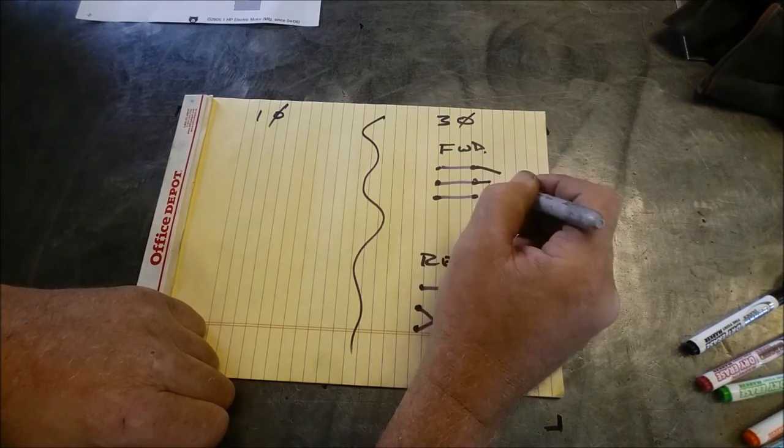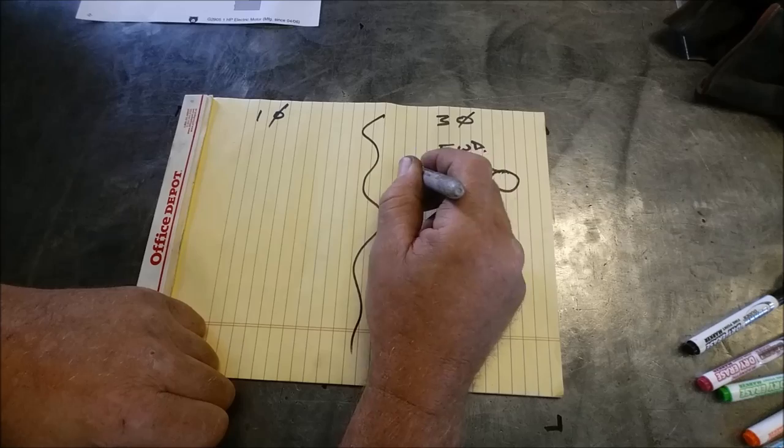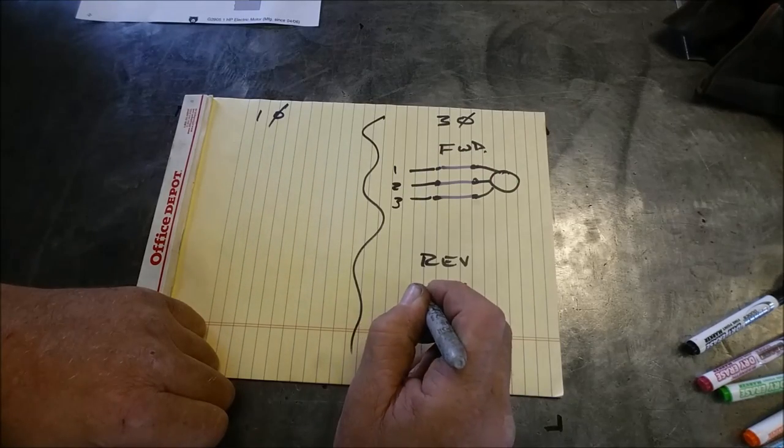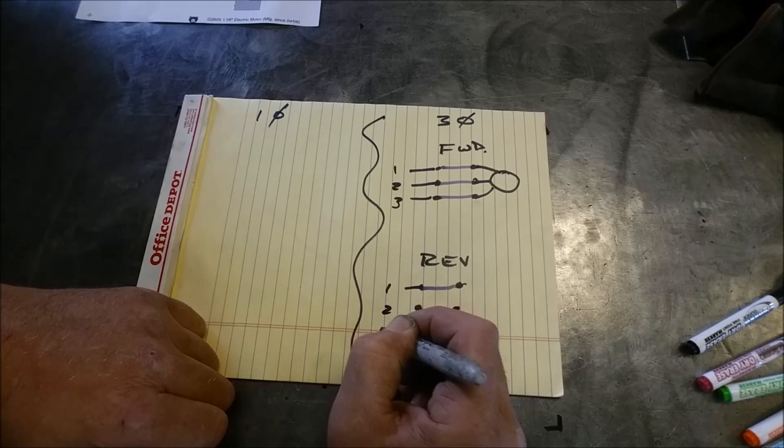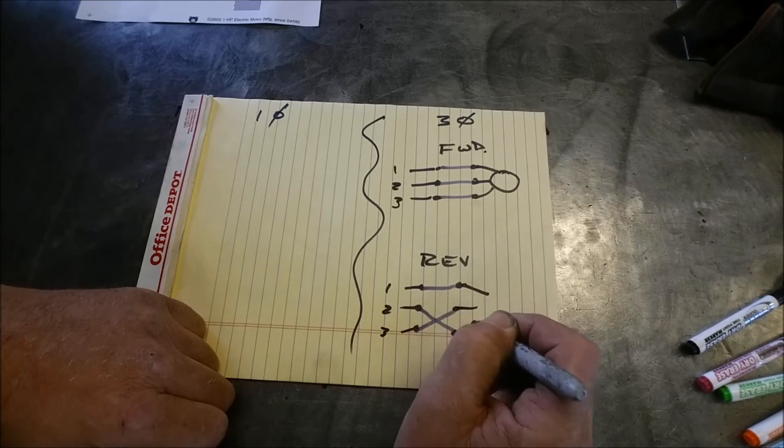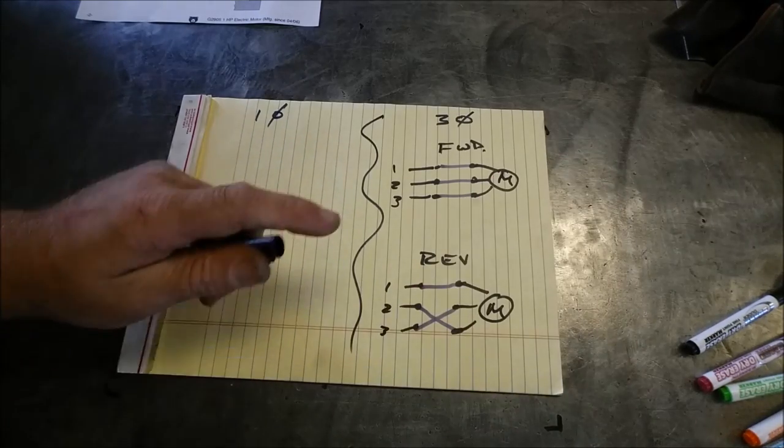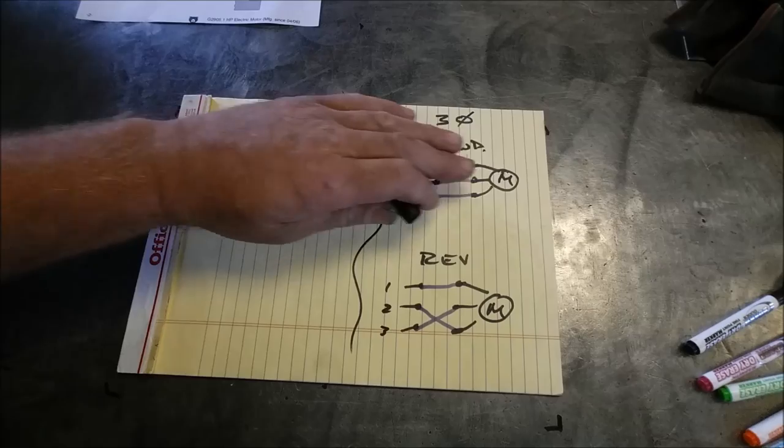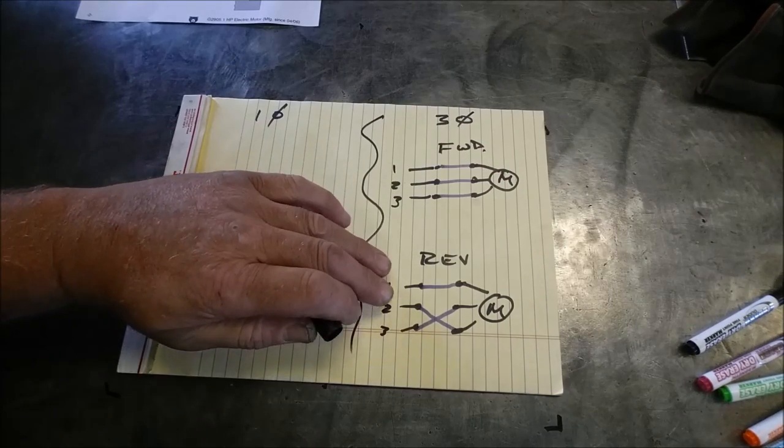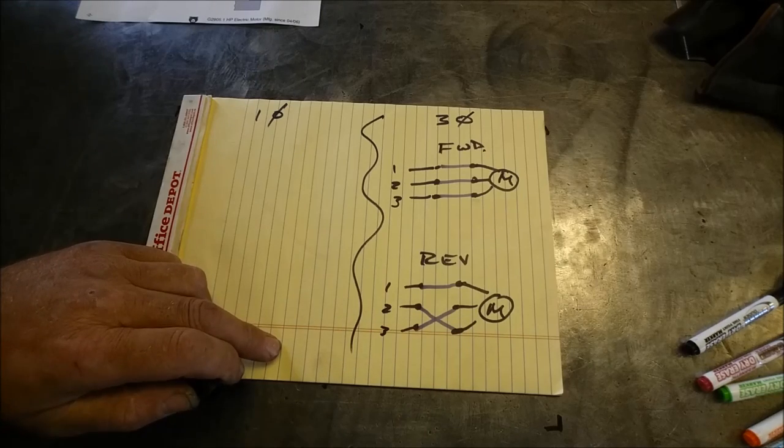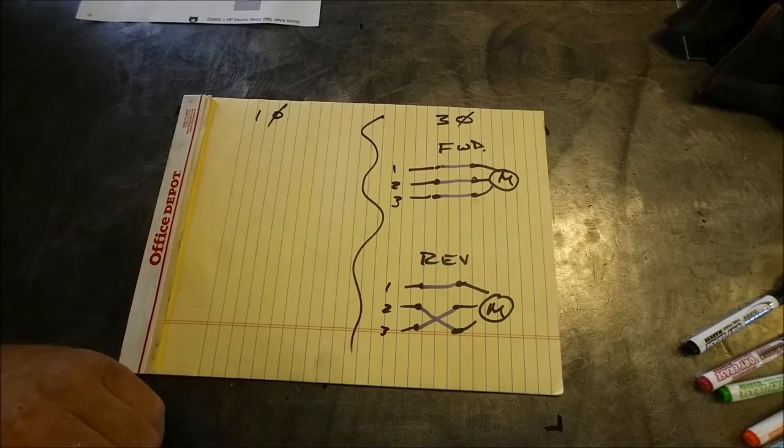This one you'd have your motor and your lines, so you'd have one, two, and three and one, two, and three here to your motor. All that does is in the forward run position sends all three phases through. In the reverse position it flips two and three and makes the motor run backwards. Really, really simple.